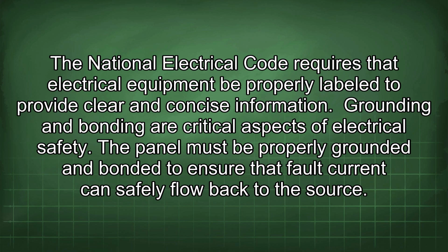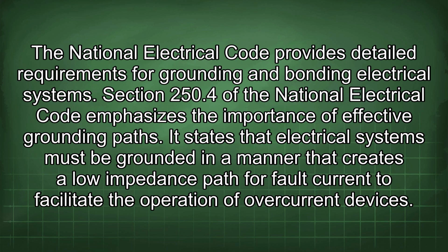Grounding and bonding are critical aspects of electrical safety. The panel must be properly grounded and bonded to ensure that fault current can safely flow back to the source. The National Electrical Code provides detailed requirements for grounding and bonding electrical systems. Section 250.4 of the National Electrical Code emphasizes the importance of effective grounding paths. It states that electrical systems must be grounded in a manner that creates a low impedance path for fault current to facilitate the operation of overcurrent devices.